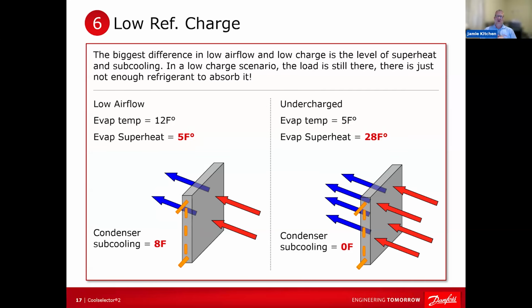All right. So let's again compare low airflow and undercharged. In a low airflow, low load situation with a TXV, the evaporator pressure and superheat both go in together. They move in the same direction, right? Because remember that diagram of the TXV? As your load goes up, your superheat slightly increases. So as long as your evaporator pressure, temperature, and superheat are moving in the same direction, that is a load-induced or load-reliant change that an adaptive device like a TXV is going to do.